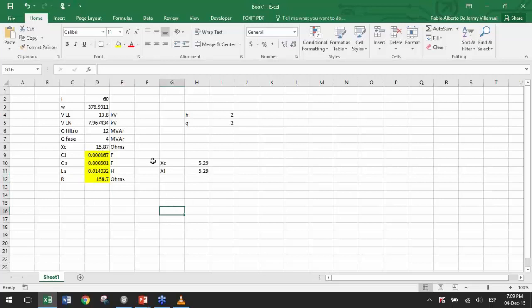And then you have the design parameters of the filter, which are XC and XL. This is the tuning branch. Now, how much resistance you need depends on the Q factor. Q is the quality factor, which is about the bandwidth of the filter. So I'm going to tune this filter to the second harmonic with a quality factor of 2. Now, all the formulas are here. I want to create a 12 MVAR filter.